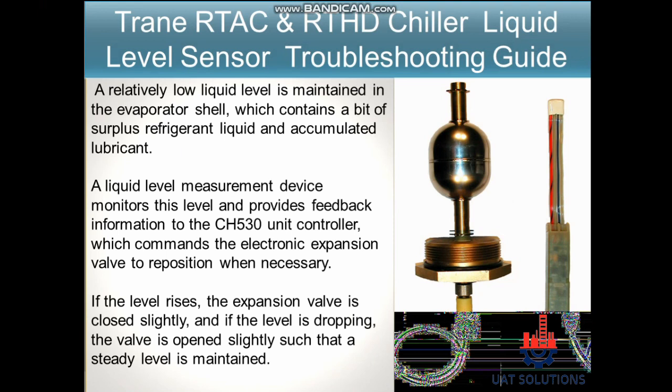A relatively low liquid level is maintained in the evaporator shell, which contains a bit of surplus refrigerant liquid and accumulated lubricant. A liquid level measurement device monitors this level and provides feedback information to the CH530 unit controller, which commands the electronic expansion valve to reposition when necessary.